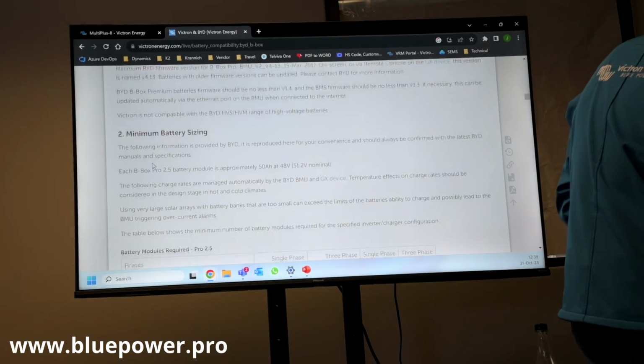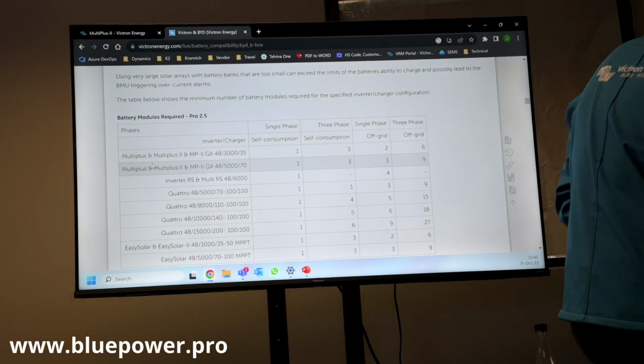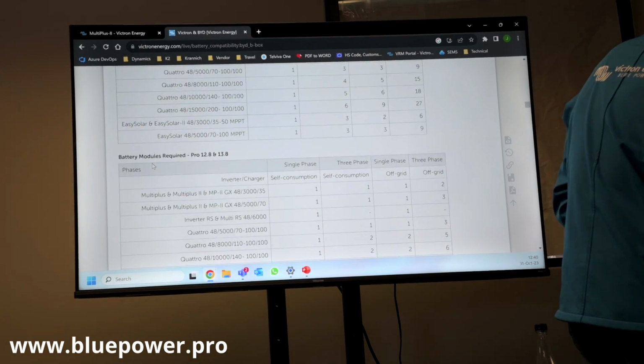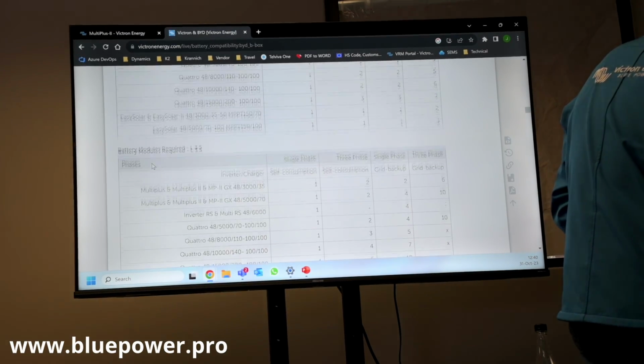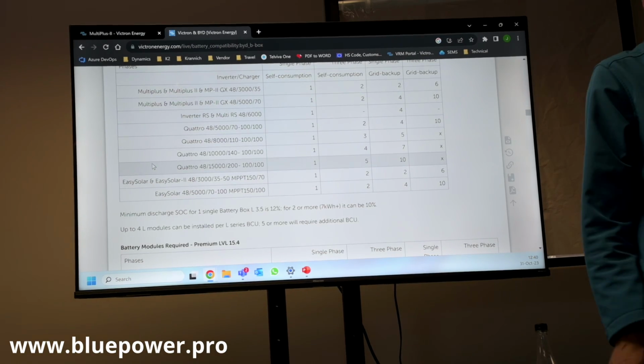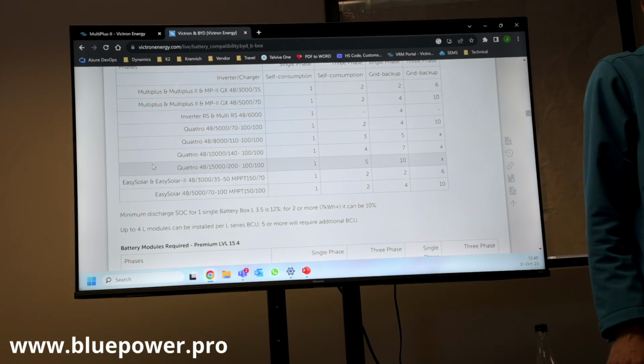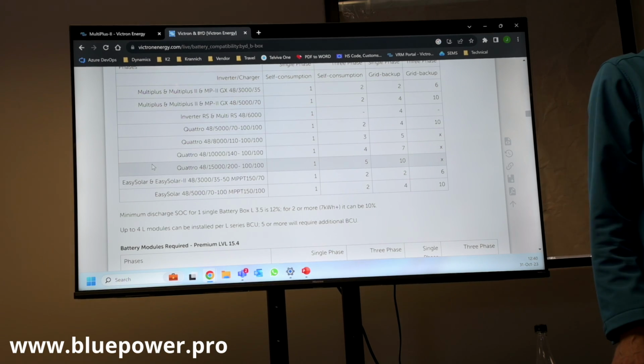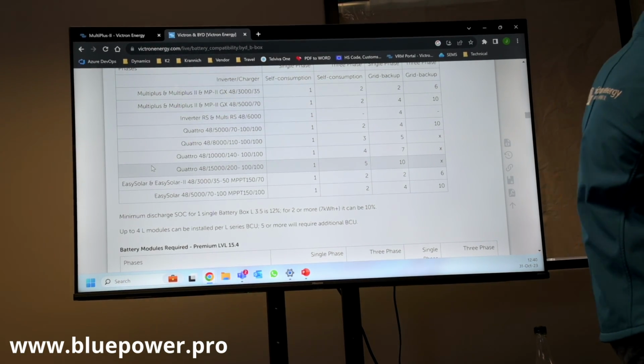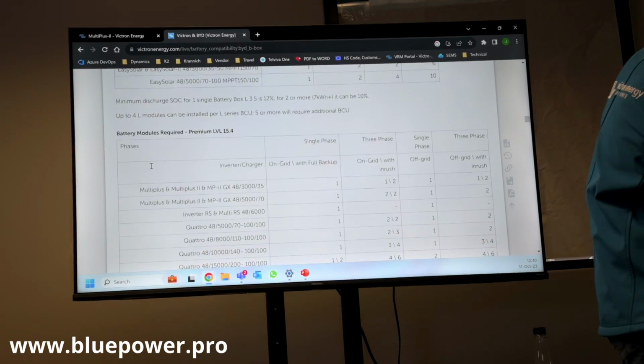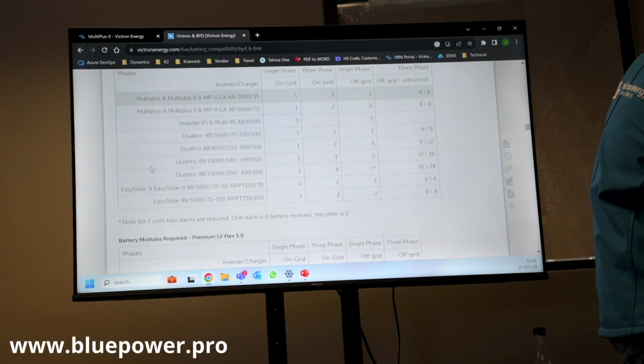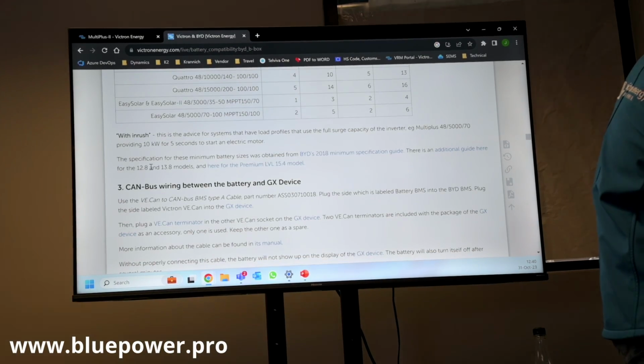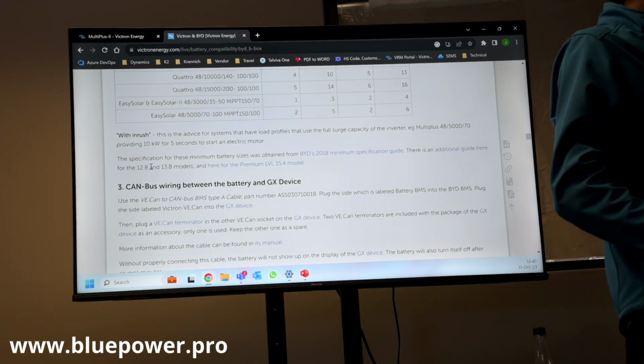Connect your comms on there as well. The startup procedure for BYD and Victron is different to what's suggested right now. Never start the battery first. All fuses closed, all communication done. Then only start the battery because it has a pre-charge resistance built in. So you can damage those circuits if you don't start up and commission the battery correctly. So you just close the whole circuit, and then the battery, and then the inverter.